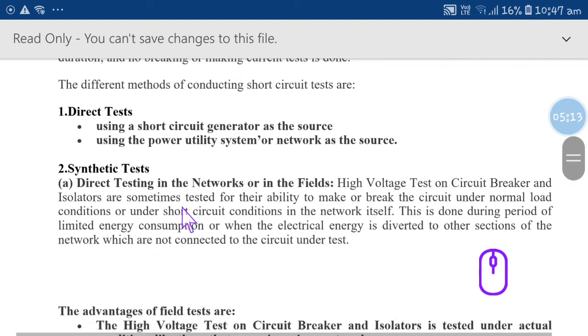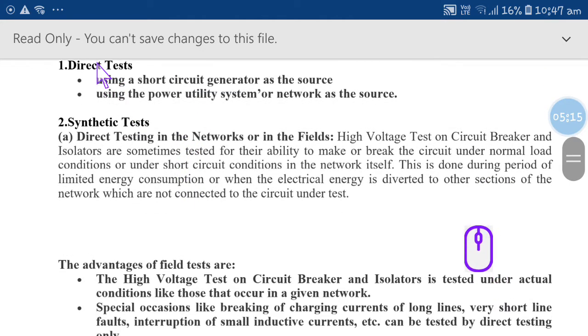So now I will go into depth here. First is the direct test. It has been asked in the question paper. In the direct test we use short circuit generators as a source, and also the power utility system or network as a source, okay. So now in the direct test, it is a short circuit generator as a source, or the power utility system or network as a source. That is the first one. Second one, synthetic test, and direct testing in the network or in the field.